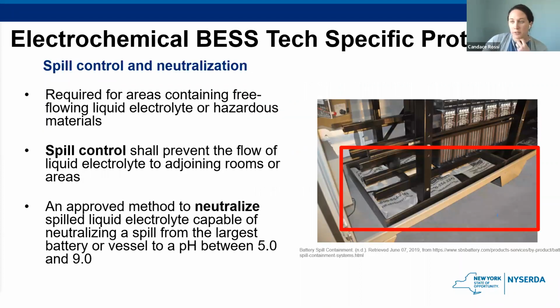So here we have the spill control and neutralization requirement. Some energy storage chemistries have a liquid corrosive electrolyte. These corrosives can burn skin and damage first responders' PPE. The responder should follow their department's standard operating procedures when responding to corrosive spills. So once again, it is really important to have the appropriate signage for the system so they know what they're dealing with, and also have that training as part of the commissioning plan for your first responders.